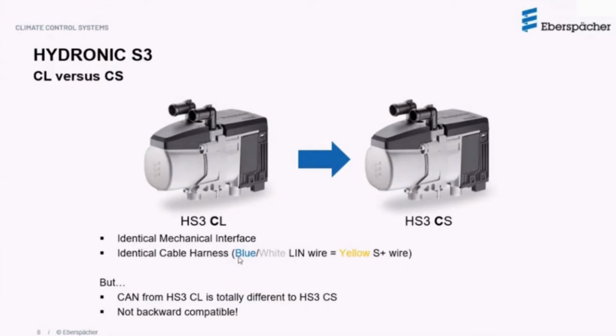In the past, our harnesses used to have the blue-white as the standard in the main heater harness. So it was a simple matter of connecting blue-white to blue-white on the controller, the Easy Start Timer, and everything was good. But with the new heaters, the harness colors have changed slightly: instead of using blue-white, we have switched over to yellow. The yellow can be used on the CS version of the heater to provide an input using the S plus signal so as to activate the heater.